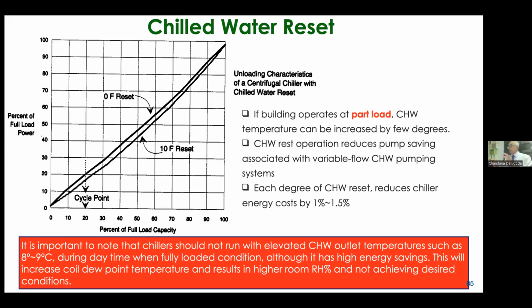Because of part load. What is part load? Building part load may be in a day. If it is early morning, sometimes night, part load. Around 12 o'clock to 3 o'clock, maybe 4 o'clock, peak. The rest is part load. What we do is raise the chill water temperature. For every 1 degree rise in chill water temperature, it saves compressor power. Chiller power saving is 1 to 1.5%. Direct savings. But the important thing is we should do this during part load.